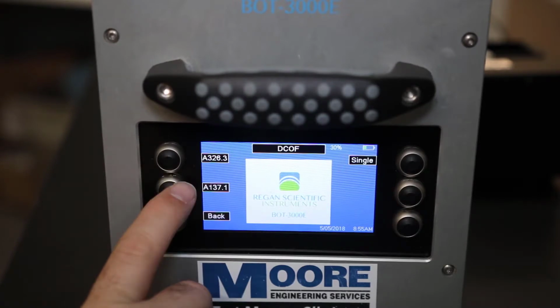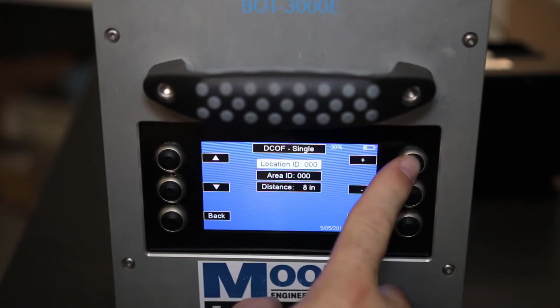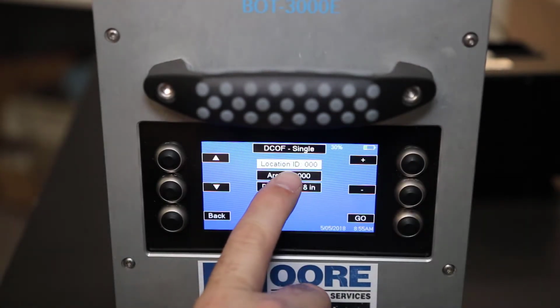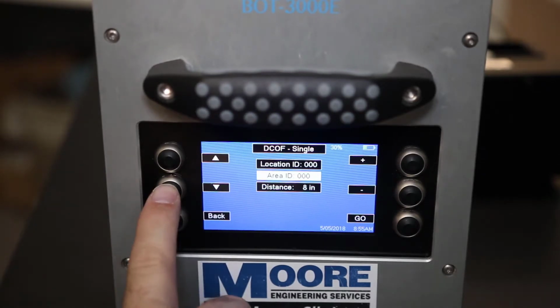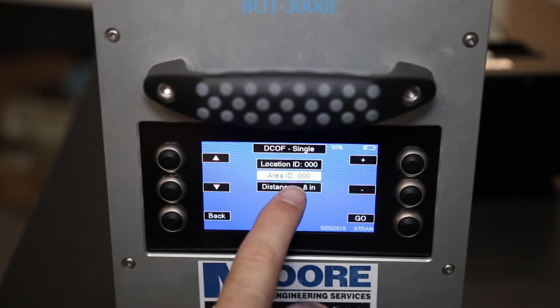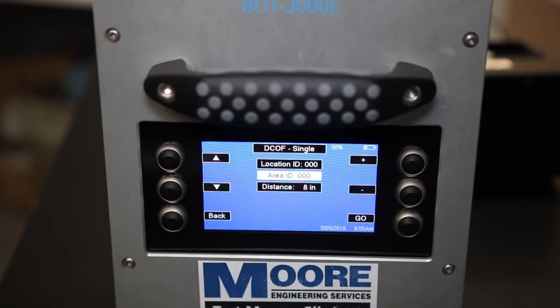As you begin taking measurements, you can assign unique identification codes to correspond to individual test locations. These codes are numerical and controlled by the user and should correspond to the different locations and areas you are testing. The location identification codes typically refer to the test locations that fell within the physical building, facilities, or sites. Area identification codes typically refer to physical buildings, floors, or other facilities.